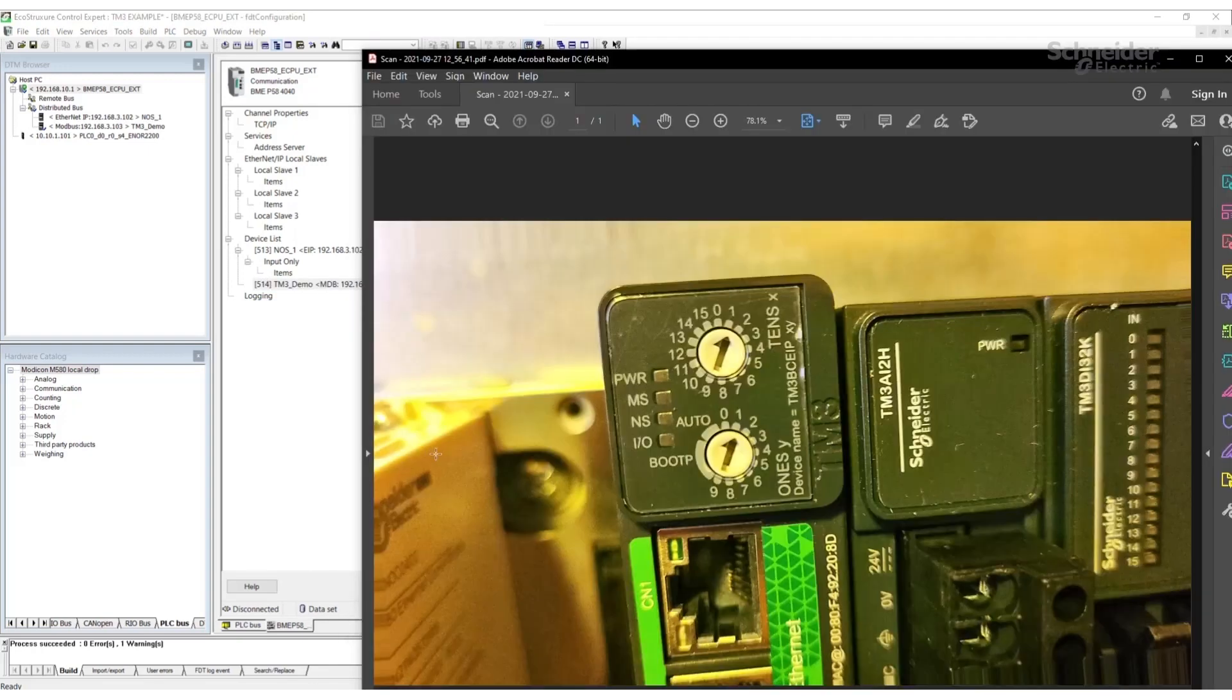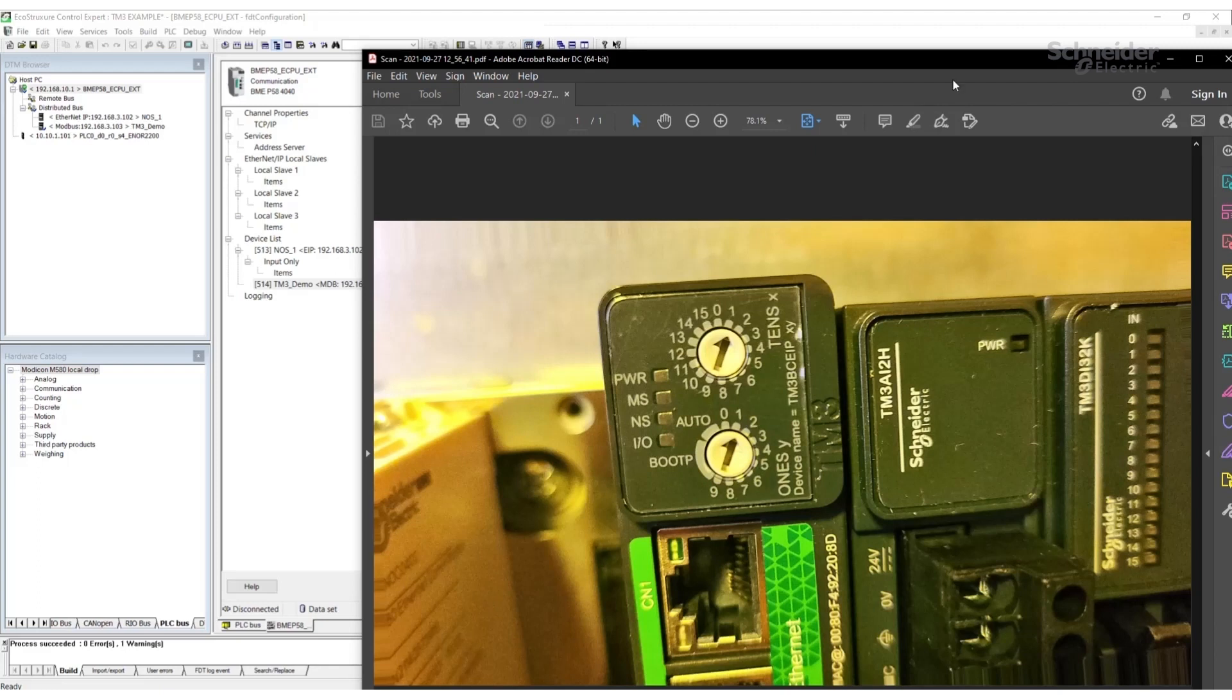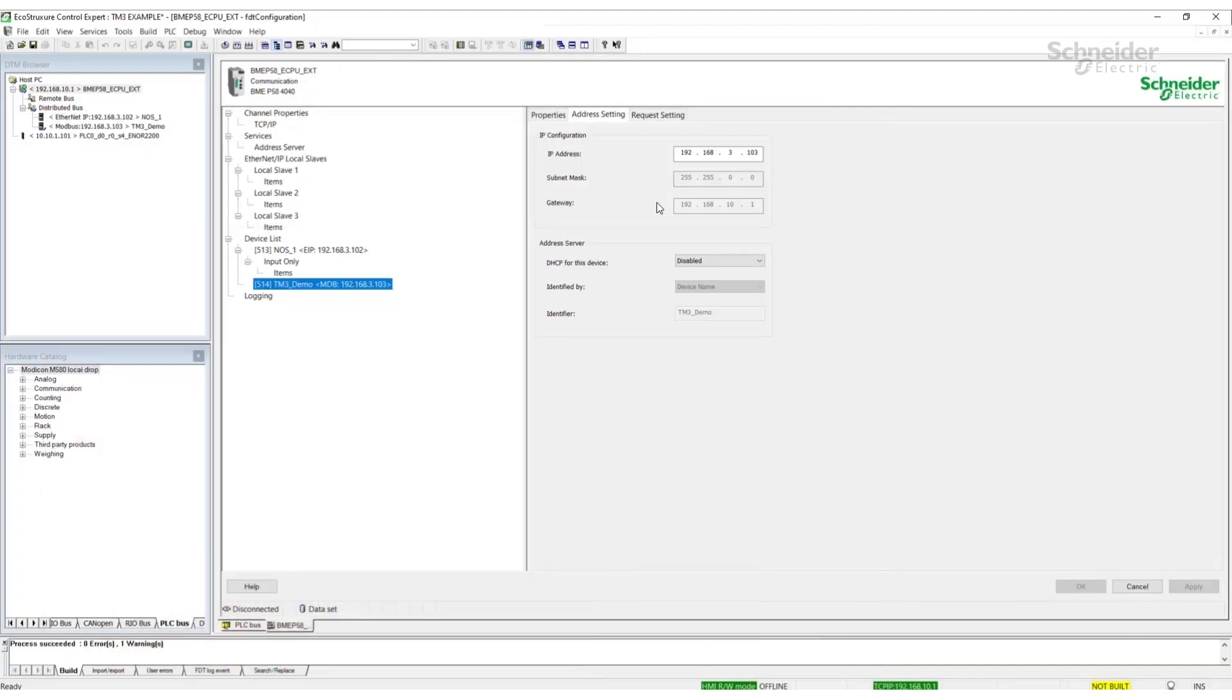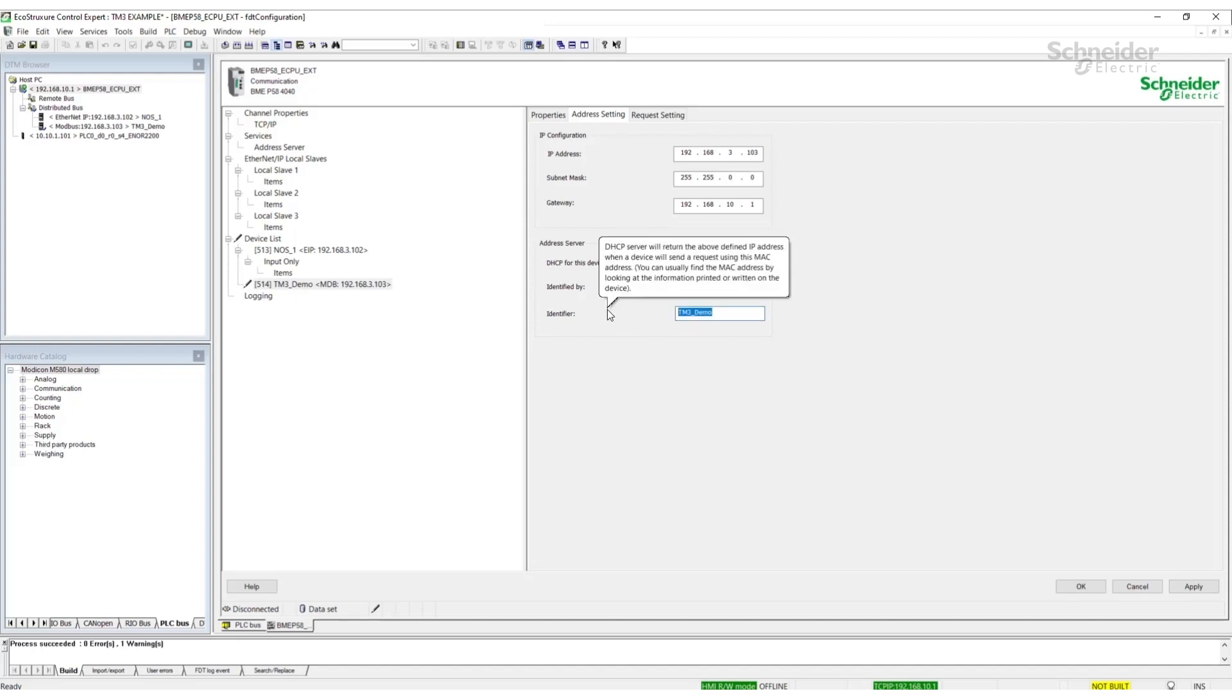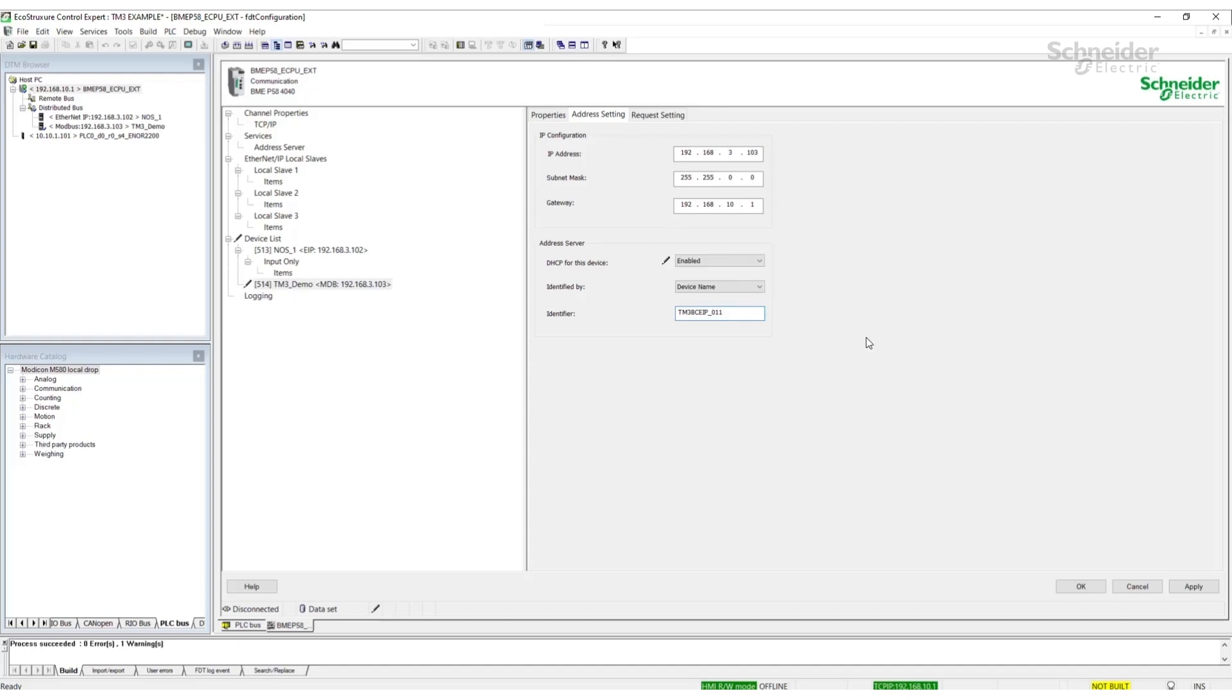For my bus coupler, I have it set to 1 in the 10s rotary and 1 on the 1s rotary. To get the address server to work for this device on the M580, I'm going to set enable to the DHCP for this device setting. Identify device name, identify by device name. The identifier for the bus coupler is TM3BCEIP underscore 10 setting, 1 setting. So in my case it's 01 for the 10s and 1 for the 1s. Set the IP address that you want it to be configured to.